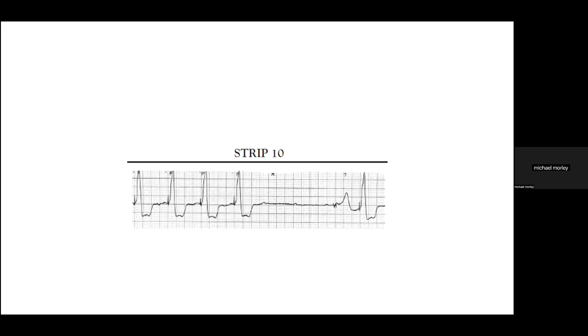Okay. So if we look at the strip, you can see we've got a pacing spike followed by QRS. Pacing spike, QRS. We've got 4 of those, so we're happy with that. What we see here then is a pause. And what we don't see is pacing spikes. So this means that the pacing system is not sending down impulses. So there is something stopping the pacemaker from sending down impulses. And this is an example of oversensing.